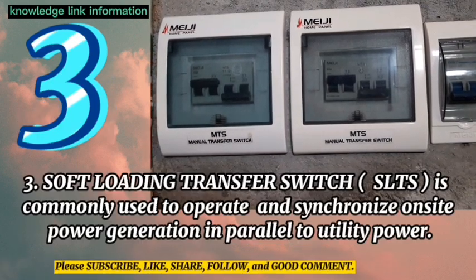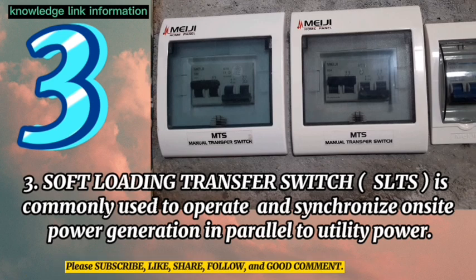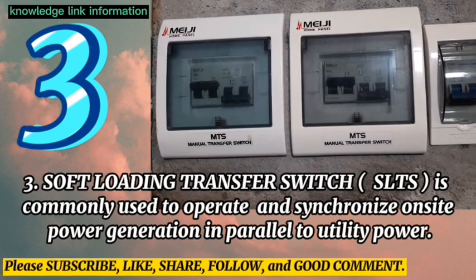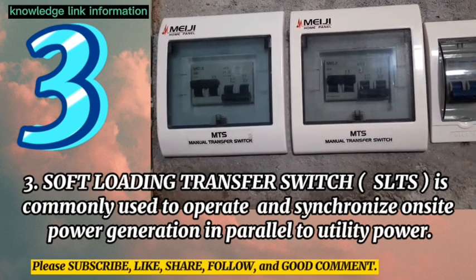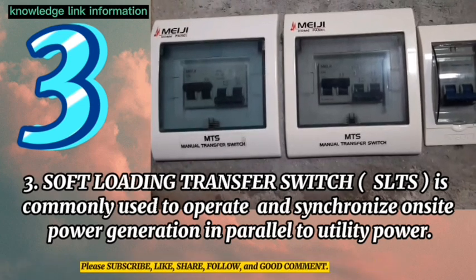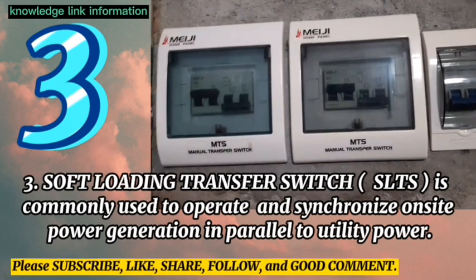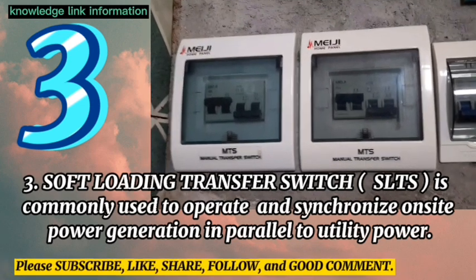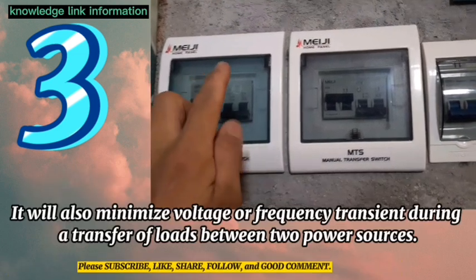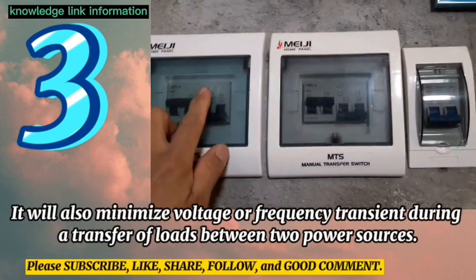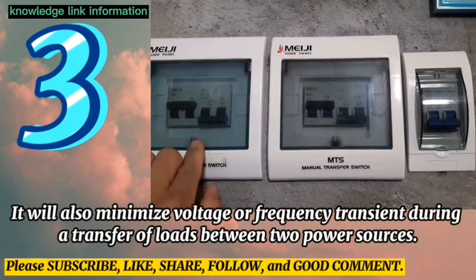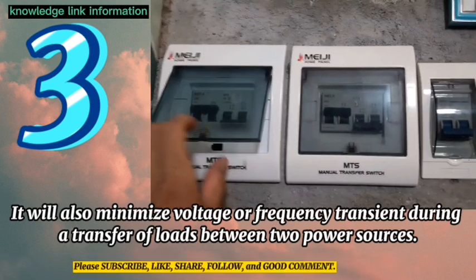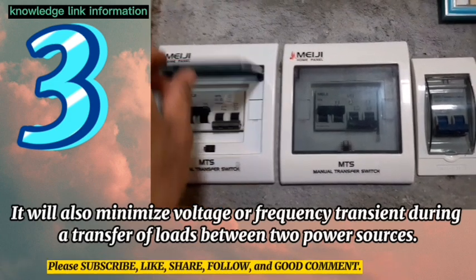Number 3. Soft loading transfer switch, SLTS, is commonly used to operate and synchronize on-site power generation in parallel to utility power. It will also minimize voltage or frequency transient during a transfer of loads between two power sources.